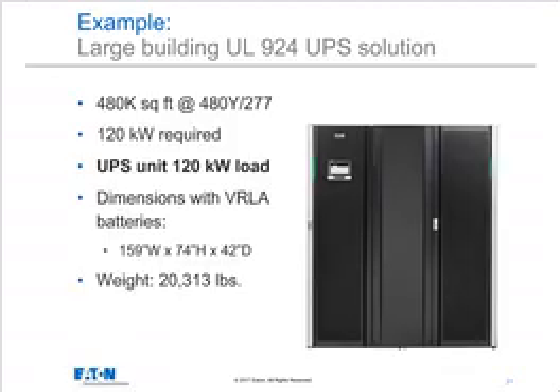In a large building, UPS is almost always 480, 277 volts, and the lighting is being operated phase to neutral 277. This shows a 120 kilowatt UPS. There are UPSs available up to 200 kilowatts, and maybe a few of them even larger than that, that are intended specifically for emergency lighting use. So the physical size of the machine gets quite a bit wider, and look at the weight there. So now I'm up to 20,000 pounds here for a system that is bigger than the box shown here. This box shows the UPS alone, not all the battery cabinets that need to go with it.